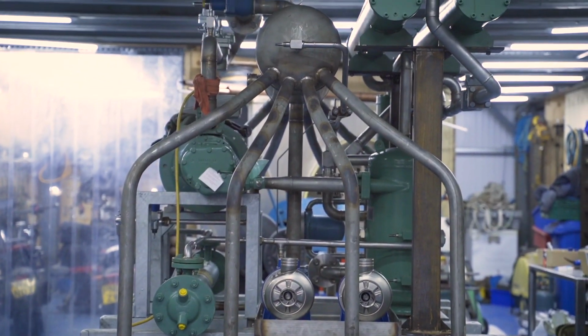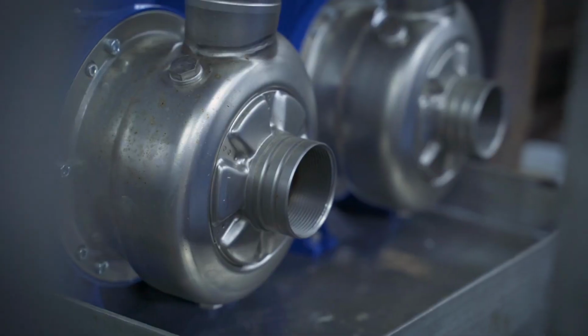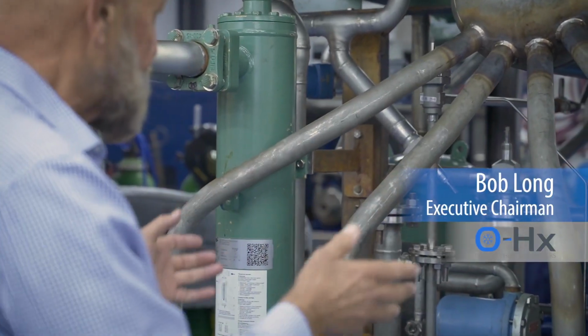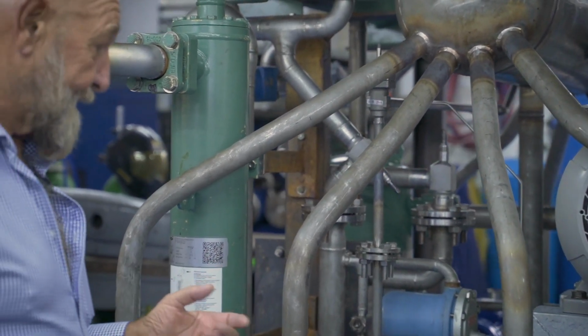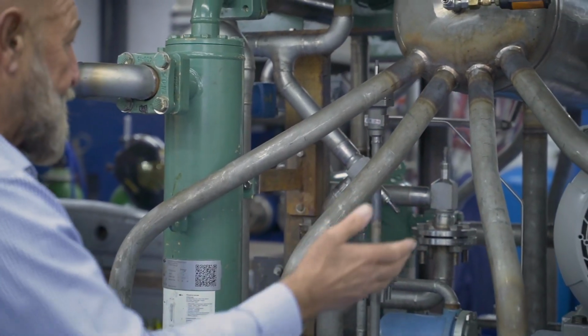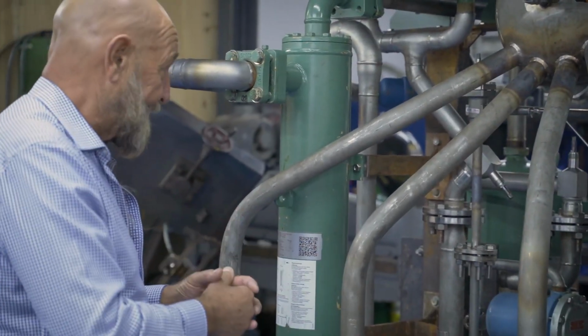You can charge up your cooling system when electricity prices are zero, negative, or at least low, and you don't have to draw electricity from the grid when prices are expensive. Ammonia refrigeration plant. We've chosen ammonia because it's got a zero global warming potential and a zero ozone depletion factor. And it's also very economical in converting electrical energy into usable cold thermal energy.